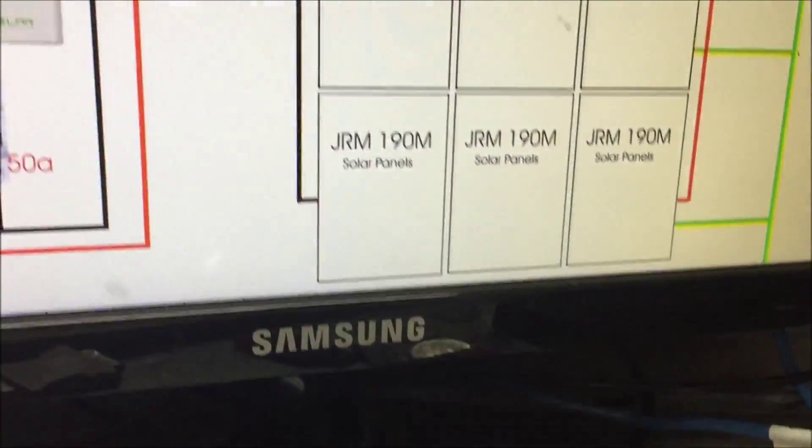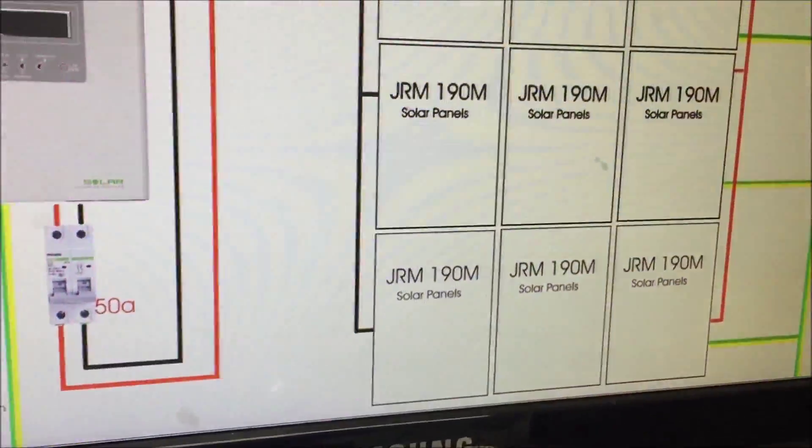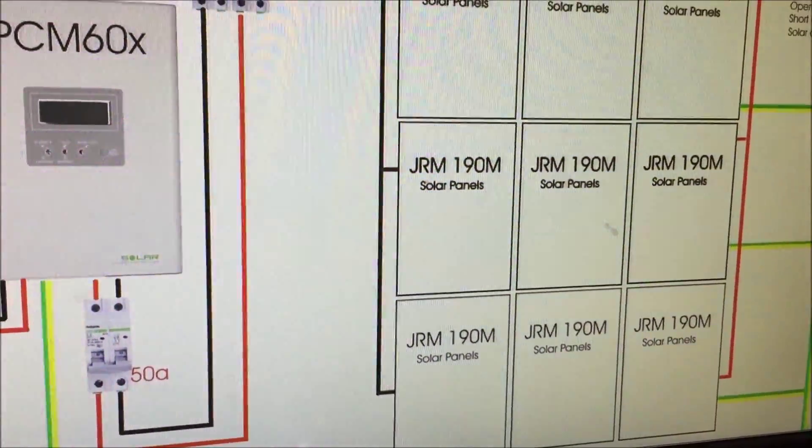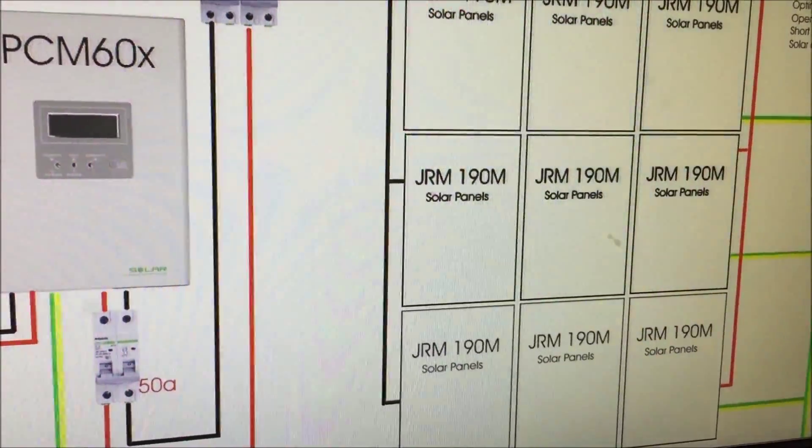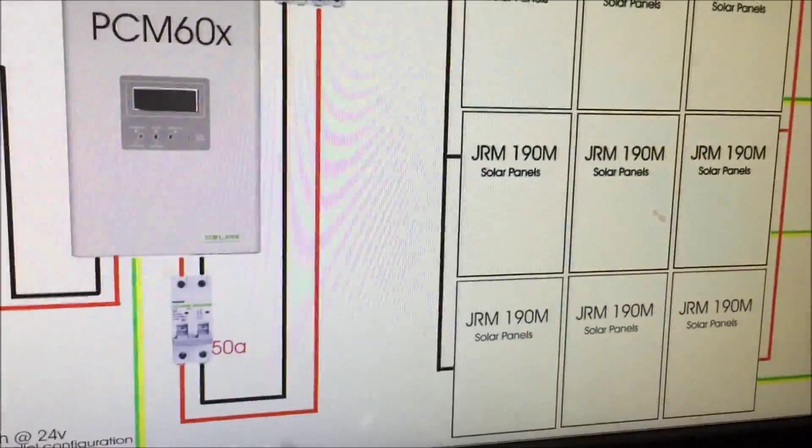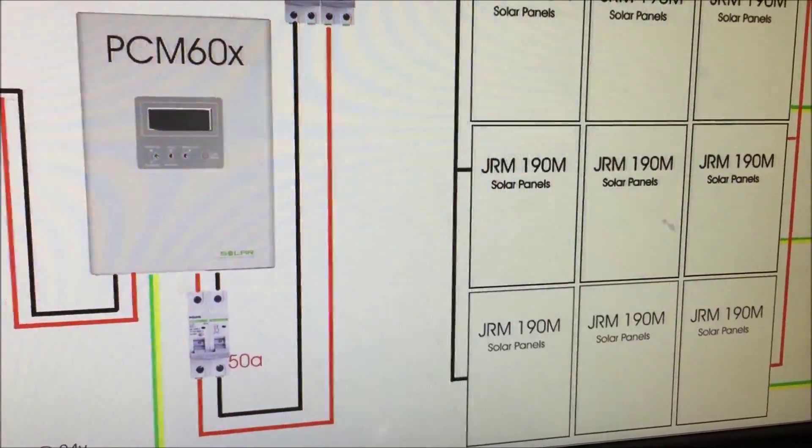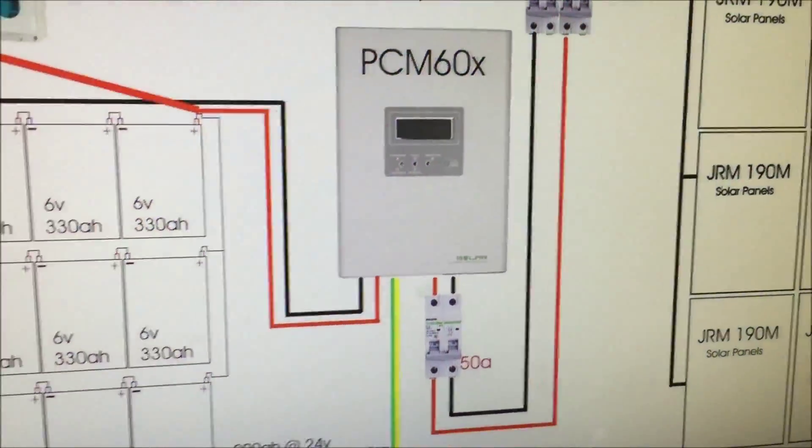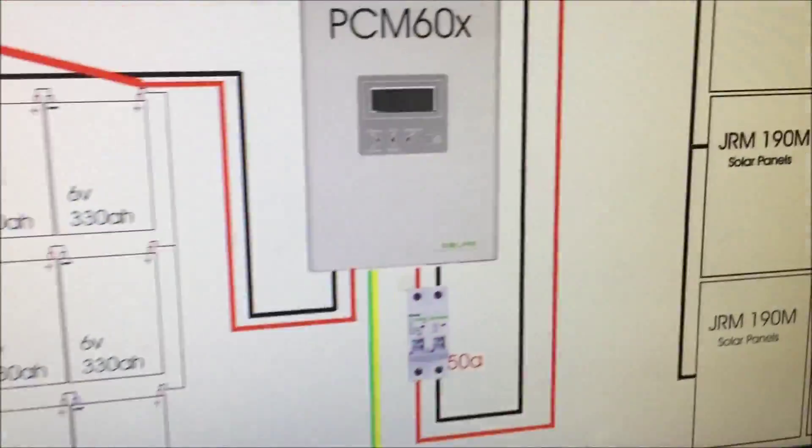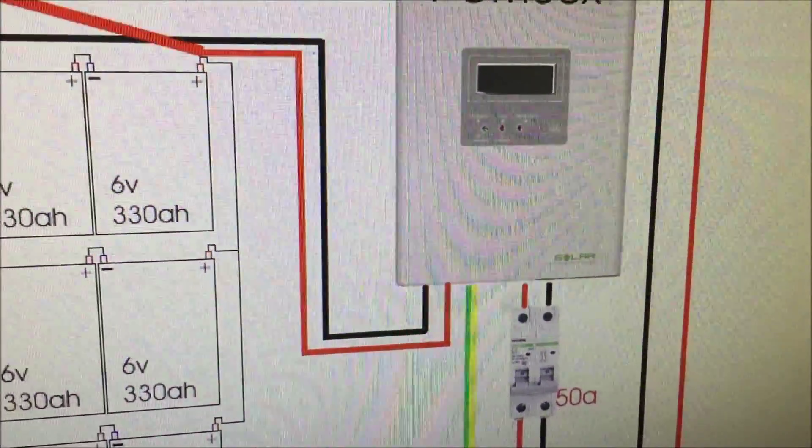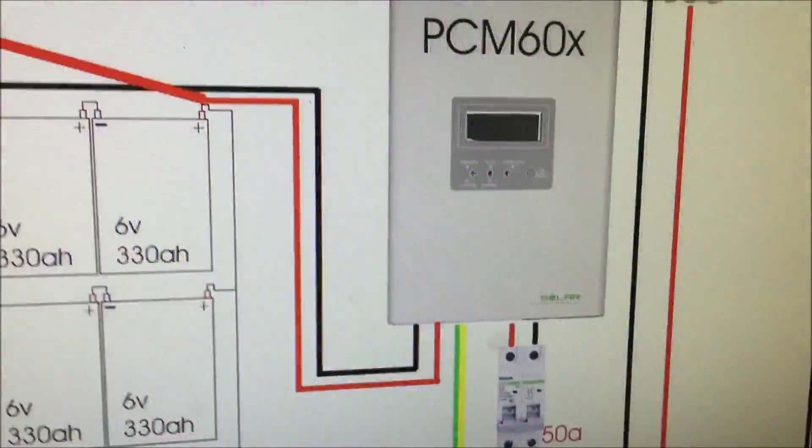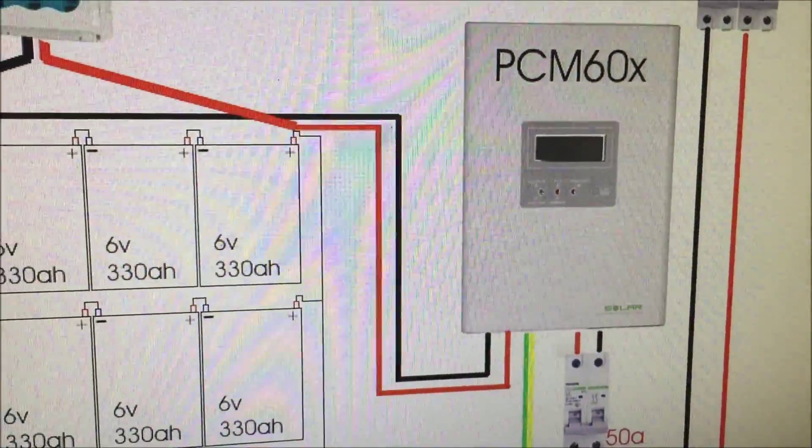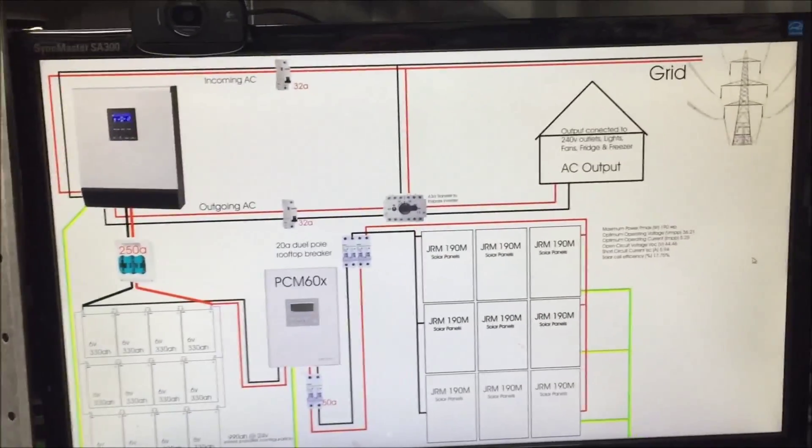Goes into my PCM60X and that's got another 50 amp breaker at the other end. That way if I have a problem in that cable anywhere someone puts a shovel through it or whatever even though it's like 50 centimeters underneath the earth and then in conduit, if someone ever breaks it at least I've sort of got a little bit more protection at both ends. And then naturally that goes into my battery bank. Now what I don't have there is I've got another circuit breaker in there. Another 100 amp circuit breaker. It is there it's just not in the picture. So that's how I've got mine set up.